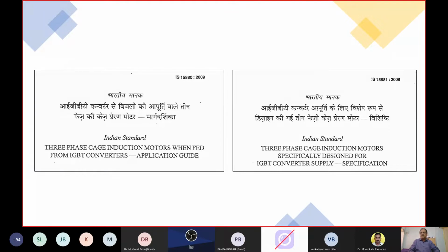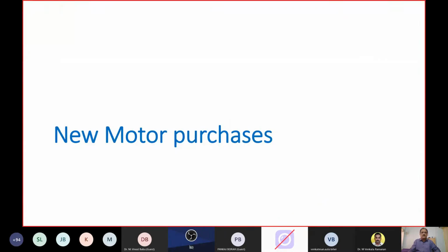Then I have put two standards in parallel. These are guides for selection of cage induction motors when used with VFD, IS 15880 and IS 15881. Again, these two standards give a wealth of information as to what should not be done when you are adopting a VFD for speed changes in your motors for a double-digit energy saving, which is available from the system. So therefore, these two standards are again very, very interesting standards. One has to read, understand, and apply them, and also use them during procurement of motors.